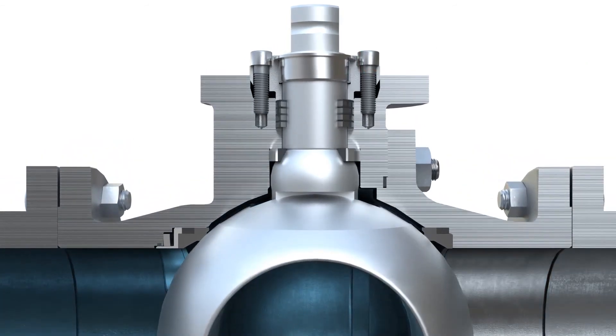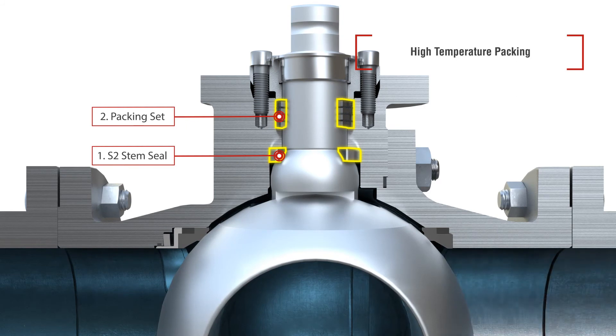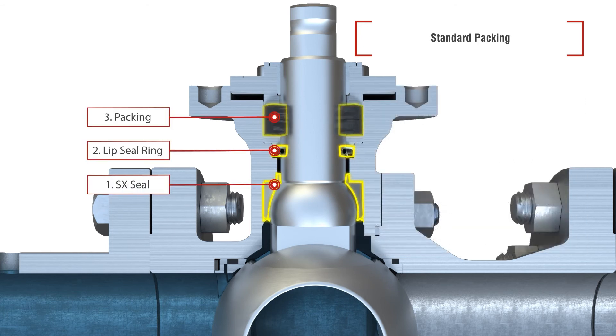Tough Seat Performance Series valves with high-temperature trim use a two-layer packing design demonstrated and certified through extensive tests by renowned third-party labs to meet API 641 and ISO 15848-1 BHC03 at 400 degrees Celsius or 750 degrees Fahrenheit — by far the most outstanding performance at such high temperatures on a standard metal-seated ball valve. Tough Seat Performance Valves with standard trim are also fully tested and certified to meet API 641 and ISO 15848-1 BH-C02 to their maximum operating temperature of 260 degrees Celsius or 500 degrees Fahrenheit, while maintaining low operating torque through the use of three distinctive sealing methods on the stem.